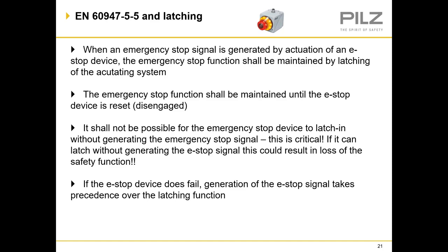As a point of interest: what is the correct failure mode of an emergency stop? If the emergency stop is triggered and the contacts change but the operator does not latch, the contacts have to open and trigger a machine stop. Although this is not desirable, this is the preferred failure mode of an emergency stop.